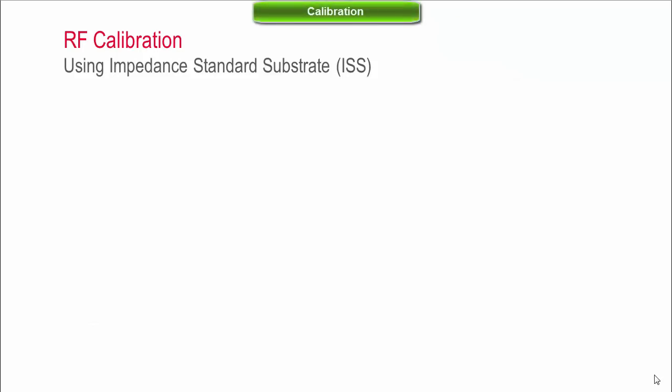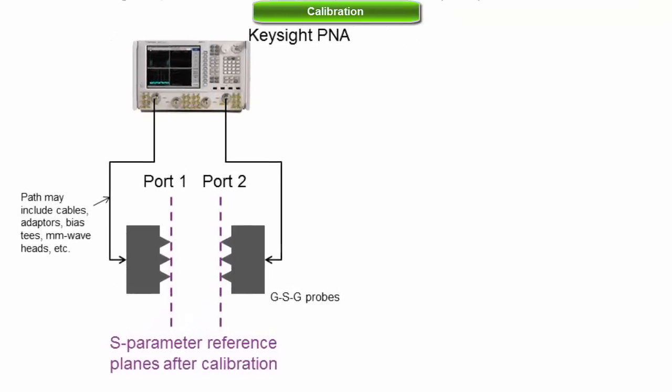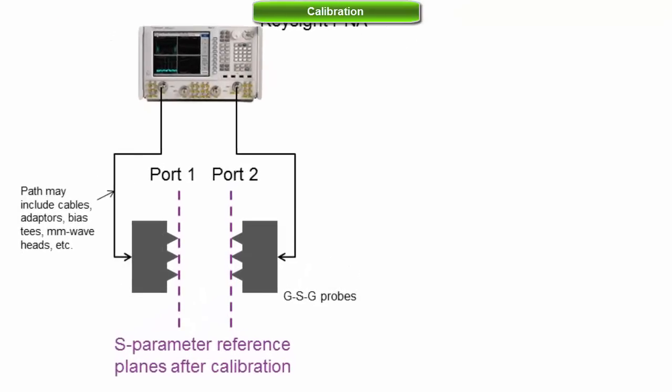Calibration shifts the S-parameter reference planes down to the probe tips and compensates for losses and phase shift due to cables and other components.